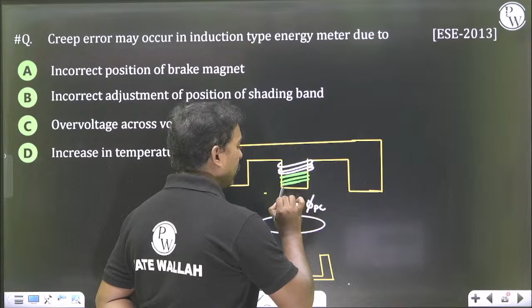When you adjust these copper shading bands, extra flux or extra voltage becomes available. Extra voltage gives extra flux. But with too much compensation, whatever current is coming through the load, sometimes even the current passing through the current coil is zero. Also, a slow rotation is possible - that is what creeping error is. That happens because of some adjustment, not incorrect adjustment - it's solvable through adjustment only.